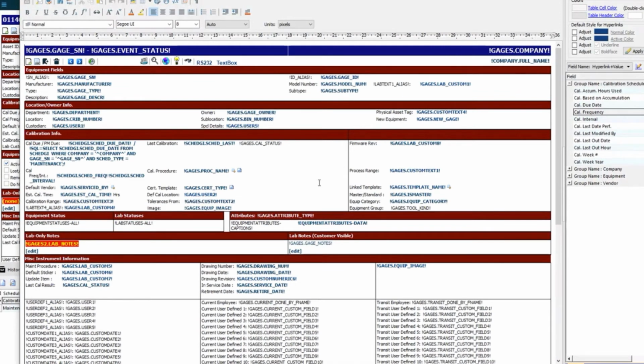Now, this is where it gets a little tricky in that some users of IndySoft have procedures for every company, particularly if you may be a manufacturer or a place with multiple sites. A Cal Lab that may be using one site has all of their procedures in one company. So that's a case where you don't necessarily need to pull it from here. You would hard code the name of your laboratory company wherever your procedures are stored.